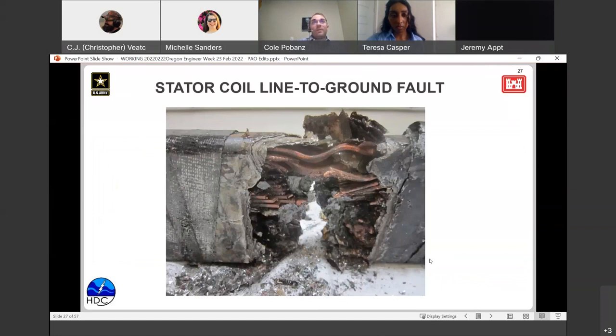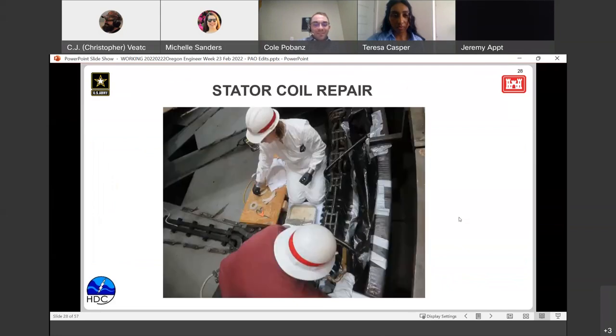What happens when one of the energized stator coils touches ground? You can see that this is pretty catastrophic and not a good thing. So when we repair a coil, we may have to take out others physically next to it because they may have exploded from the high energy running through that coil. We might also have to take out some that are electrically next to it. For example, we had to replace about 12 coils in this job one of my coworkers is doing.